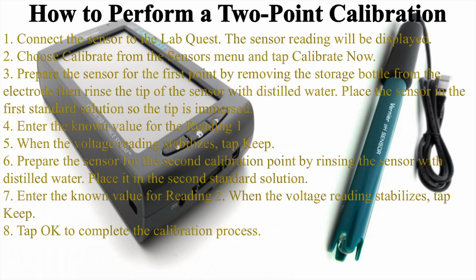How to perform a 2-point calibration. 1. Connect the sensor to the LabQuest. The sensor reading will be displayed. 2. Choose Calibrate from the sensor's menu and tap Calibrate now. 3. Prepare the sensor for the first point by removing the storage bottle from the electrode, then rinse the tip of the sensor with distilled water. Place the sensor in the first standard solution so the tip is immersed. 4. Enter the known value for reading 1. 5. When the voltage reading stabilizes, tap Keep.